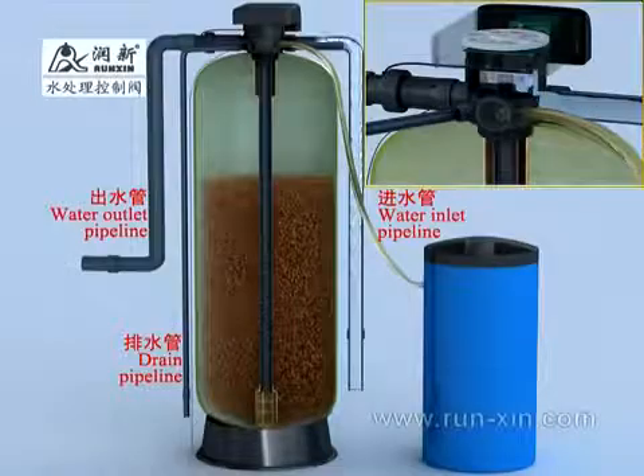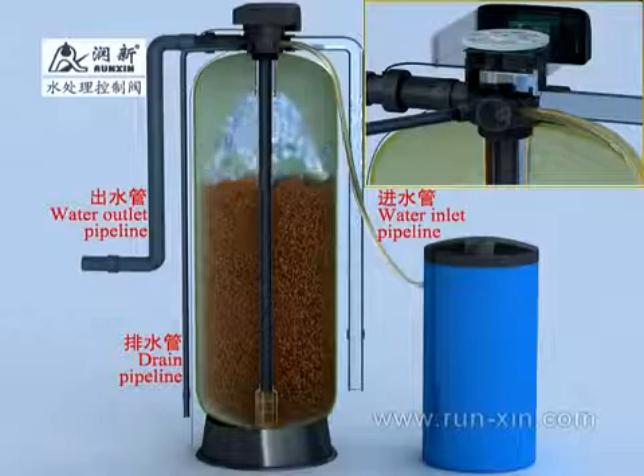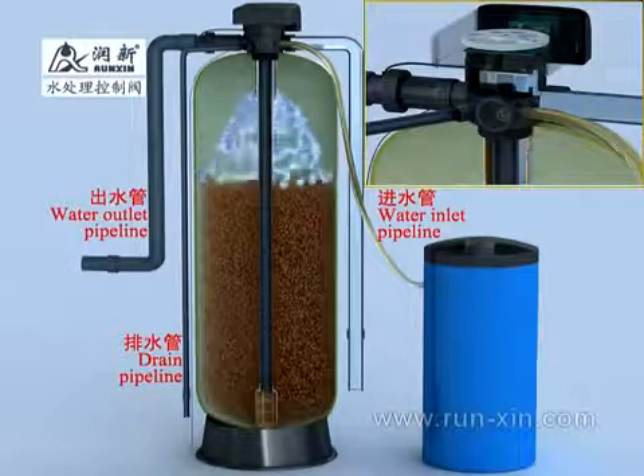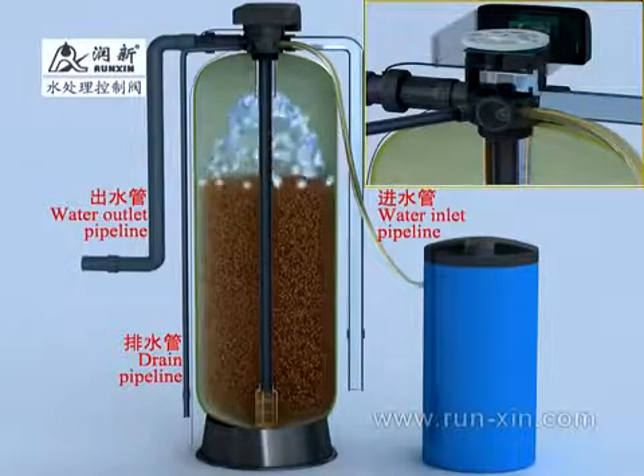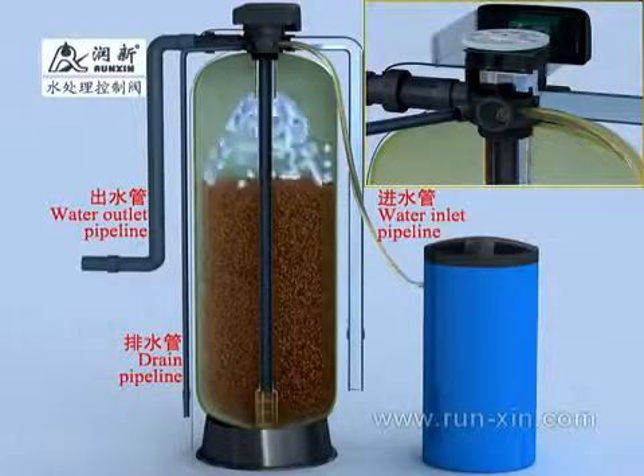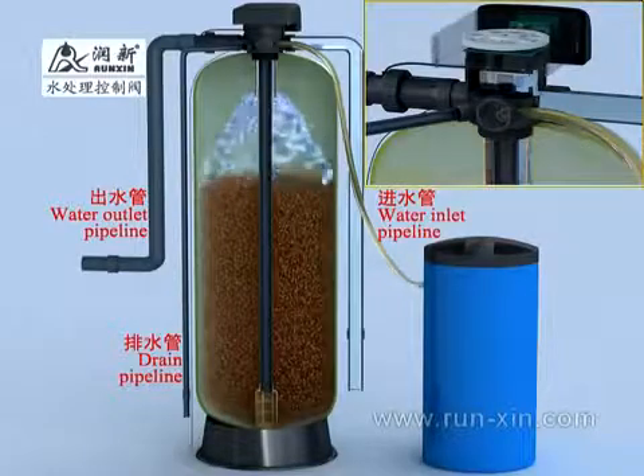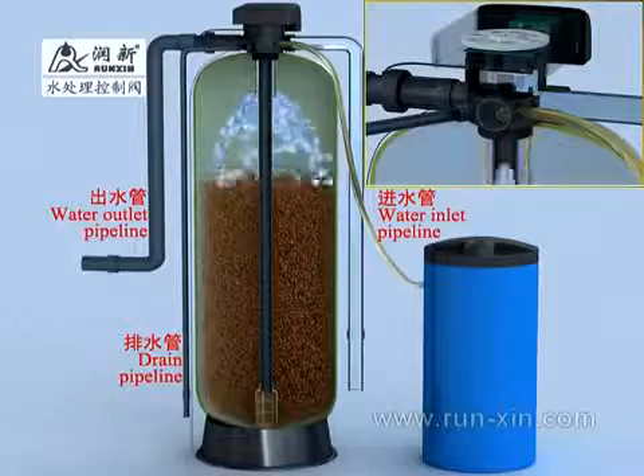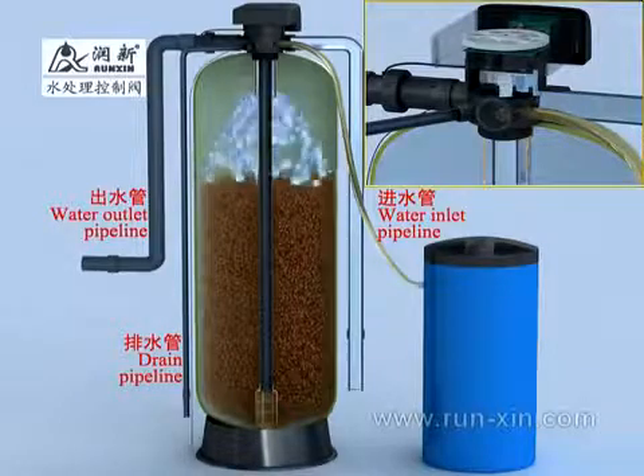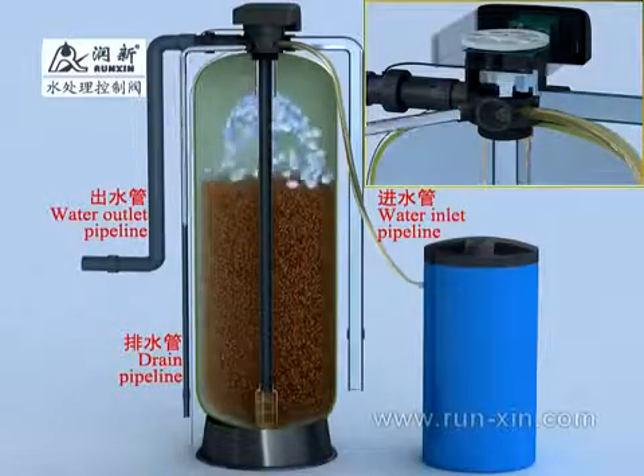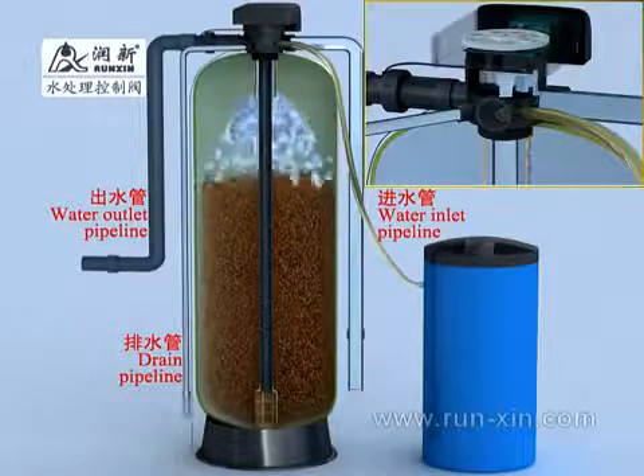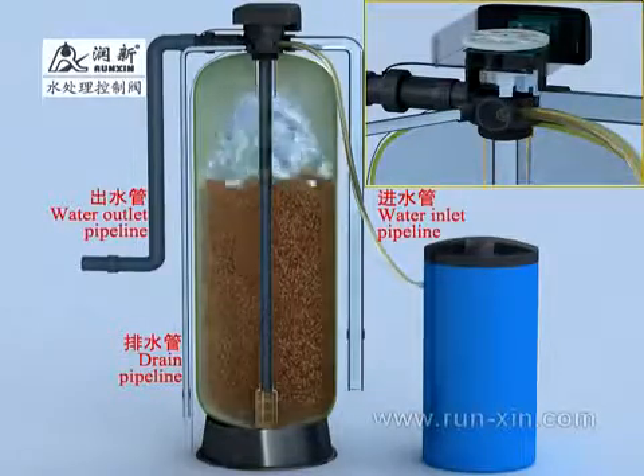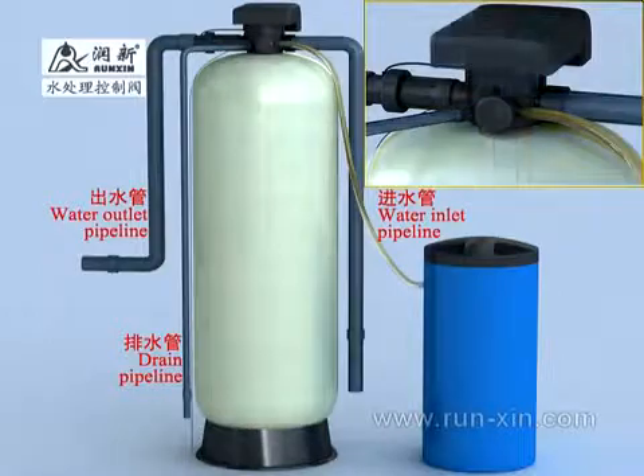Raw water flows into the control valve through the water inlet, from the top of the valve core to the valve body, through the top strainer to the tank, then past the bottom strainer to the riser pipe, finally through the valve core. The residual brine is discharged from the drain outlet. When fast rinse time reduces to 0, it is over. The system enters into service state.